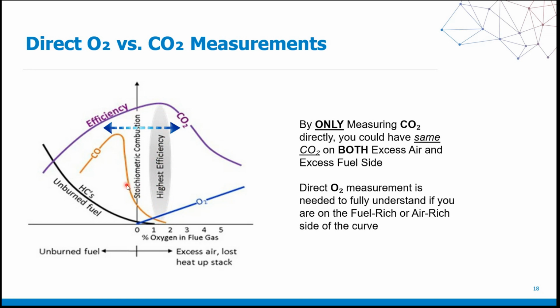But if we go to the fuel-rich side, look at what happens to our CO. If we negate what oxygen is and just pay attention to CO2, look at how high our CO is over here. This is where those of you who've ever spiked your CO sensor by doing a combustion analysis, this is what's happened. Out of all the adjustments that you make to a system, your CO is going to shoot through the roof. And you see over here that we have very, very high levels of CO, far beyond what the acceptable levels are.